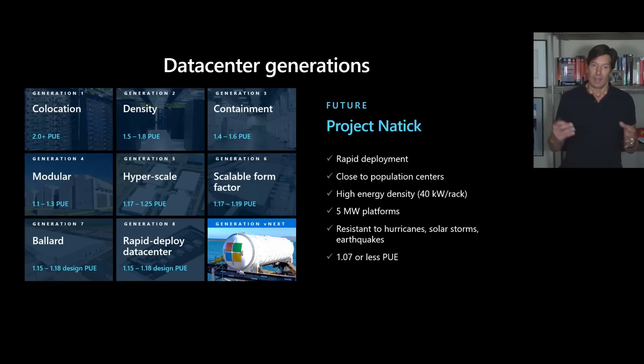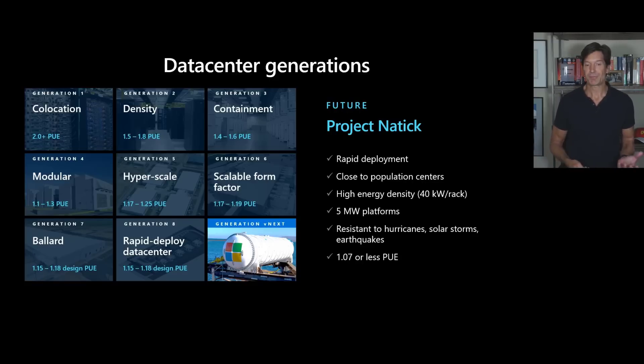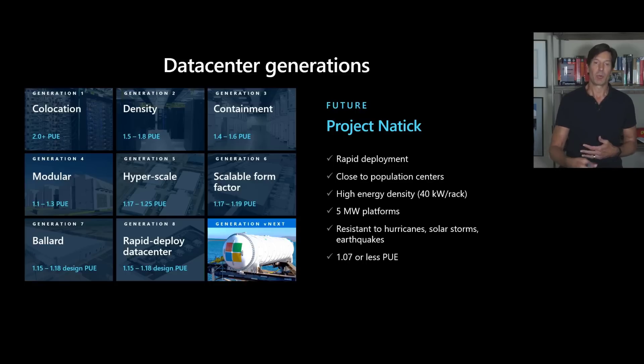One key consideration is that since these are sealed on the ocean floor, we can't service them the way we do land-based data centers — we can't just go replace a faulty server. We've got to go to a fail-in-place model where servers degrade as they fail over time. Once the number of servers in a container drops to a certain threshold, we replace the whole cylinder — deploying a new one alongside the old one, migrating data and workloads, pulling up the old one, refurbishing it, and redeploying it. This model is based on the premise that with inert gas and constant ocean floor temperature, servers will actually be much more reliable than land-based versions. At current land-based failure rates, the fail-in-place model just wouldn't work.